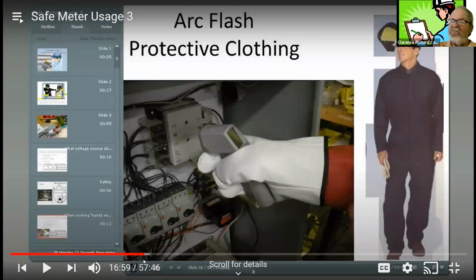This is 480 in there. We've got a circuit breaker in there that trips at 30 amps, and this is for 480 volts. That's going to have a smaller arc than you're going to have if you have a breaker that's 100 amps and 480 volts.